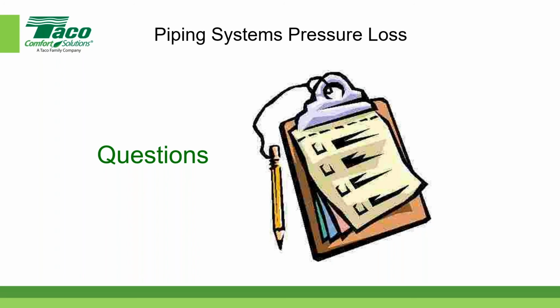When it comes to HVAC, we're talking about closed systems, with the exception of open cooling tower systems. But the majority of hydronic systems, hot water and chilled water for heating, ventilating and air conditioning, are closed systems. The water is treated, and the chemicals reduce the amount of corrosion in the piping.